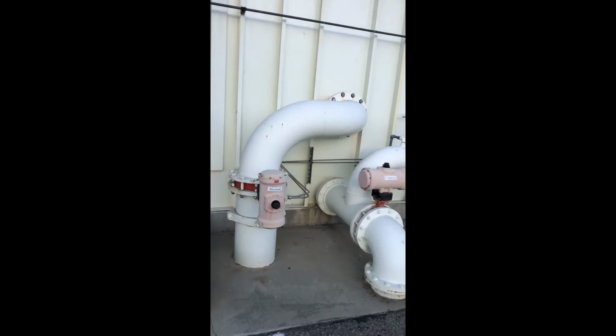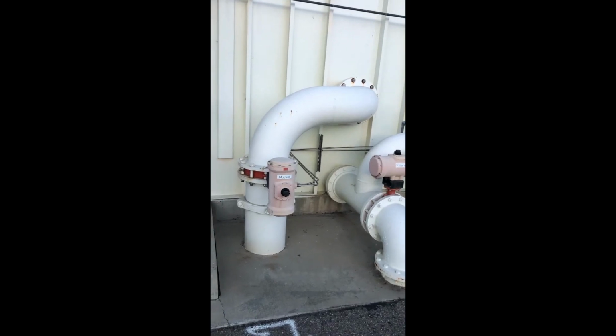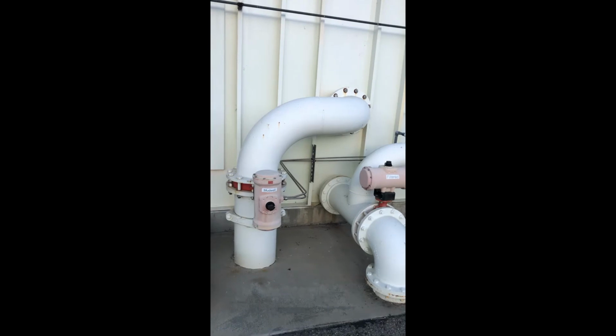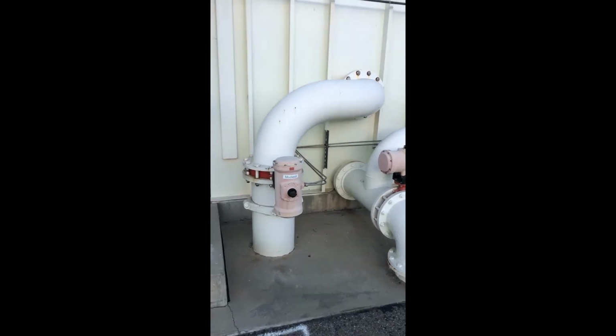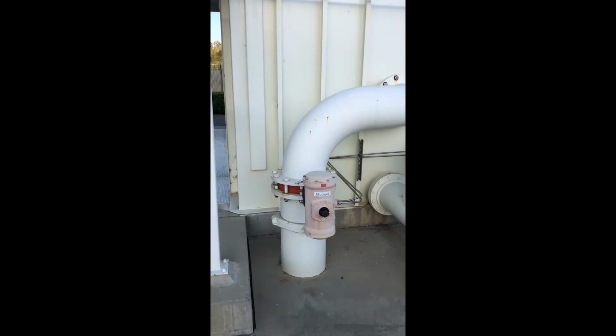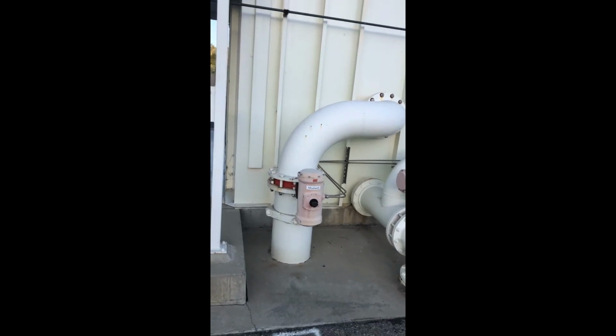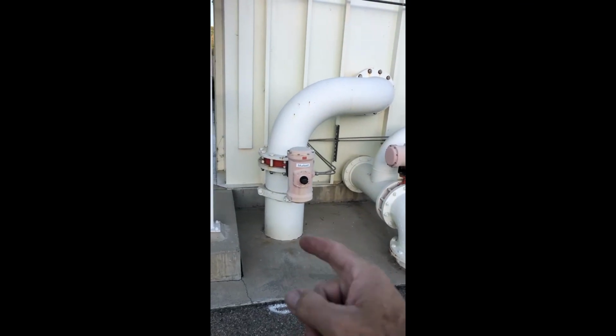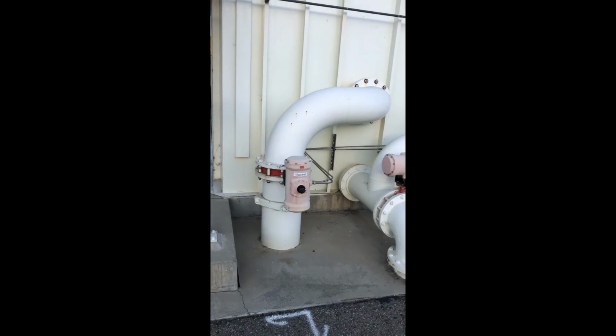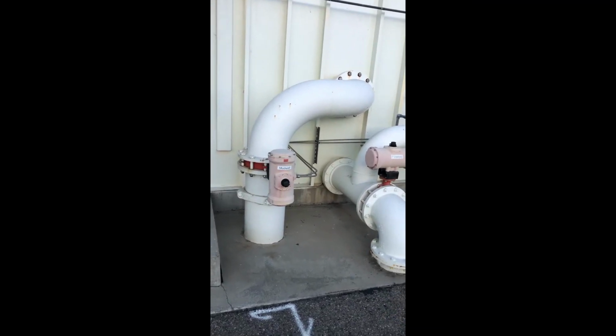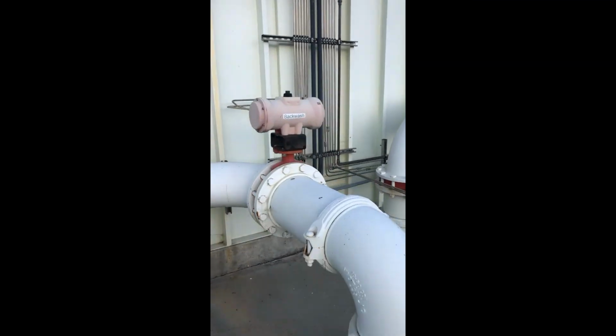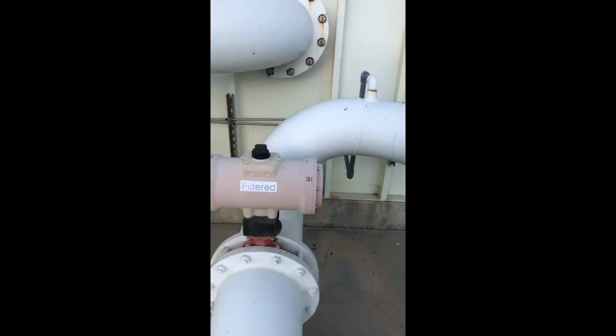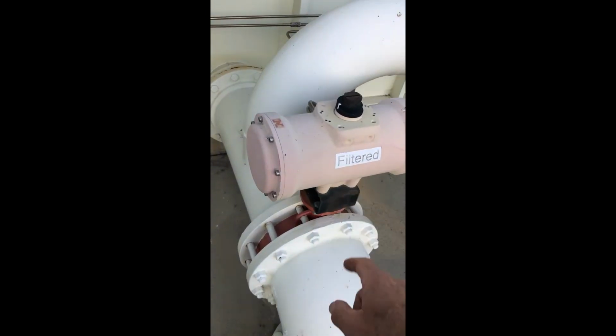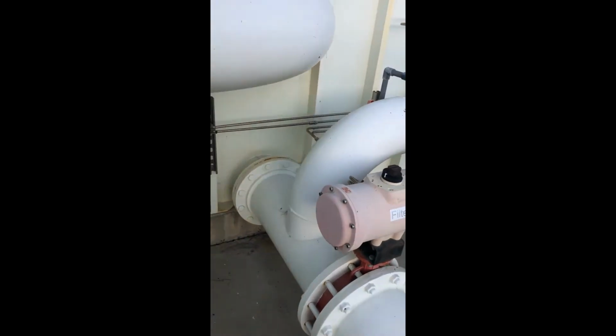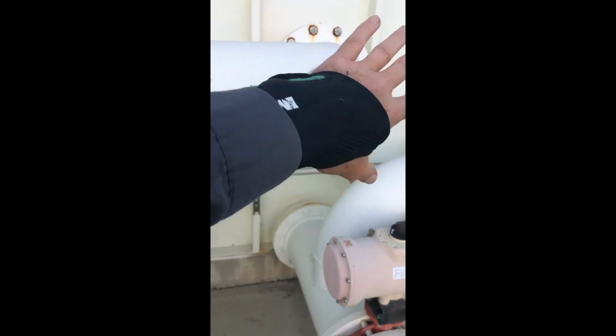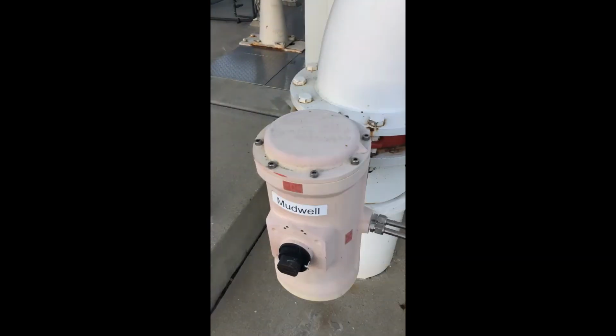the level's high, it's time to backwash, it kicks in a sequence. The first thing that happens is the inlet valve that was up top closes, so we don't feed it anymore, okay? And then this mud well valve is going to open, it's going to drain down the tank, and we'll drain it down about 3/4 of the way, okay? Then what we're going to do is this backwash valve is going to open. This filtered valve, that's the water that's coming out, is going to close, and we're going to reverse the flow through the sand and push all that crap up out of the sand bed, and it's going to be pushed up and out, and then come out of this and go into what we call the mud well, okay?